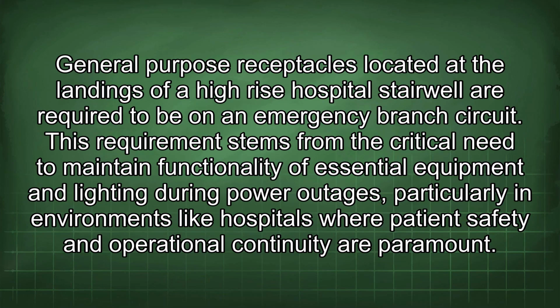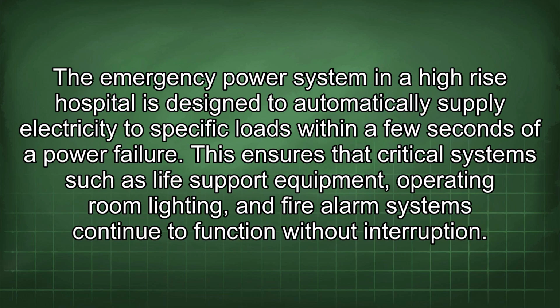General-purpose receptacles located at the landings of a high-rise hospital stairwell are required to be on an emergency branch circuit. This requirement stems from the critical need to maintain functionality of essential equipment and lighting during power outages, particularly in environments like hospitals where patient safety and operational continuity are paramount. The emergency power system in a high-rise hospital is designed to automatically supply electricity to specific loads within a few seconds of a power failure.